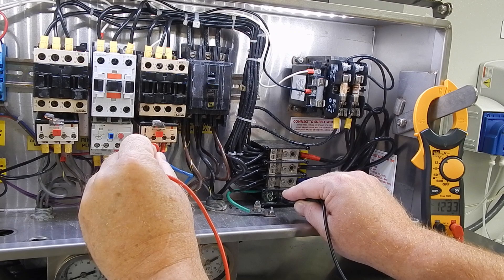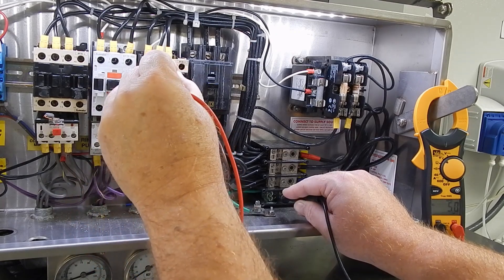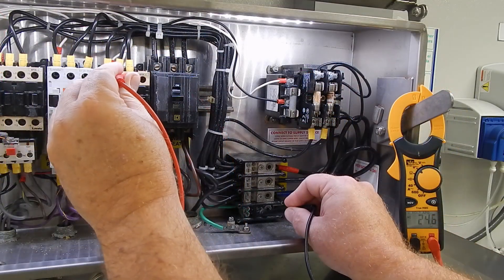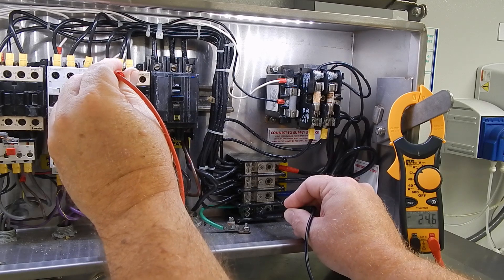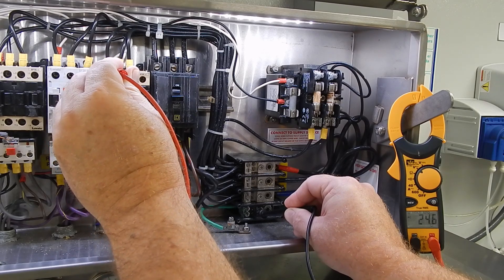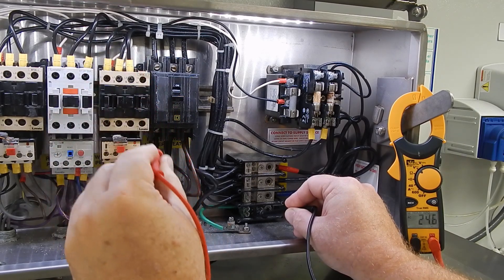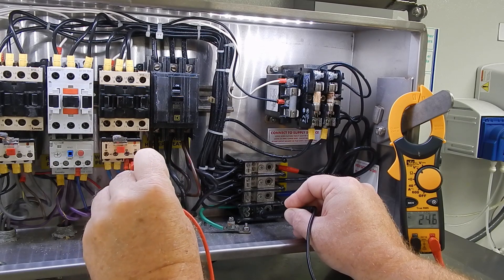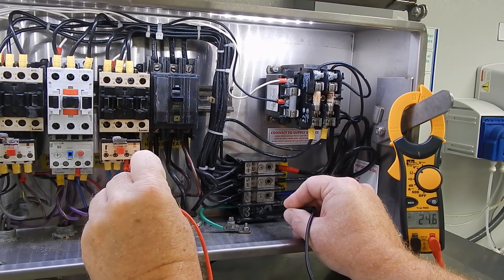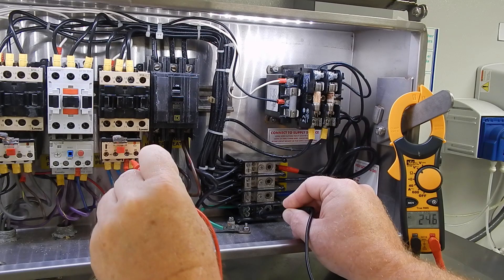The motor must be engaged to be able to test this. Here we are showing on L3 that we have low voltage or we have dropped the leg of the three phase outlet. We are verifying on the discharge side we have lost the three phase.